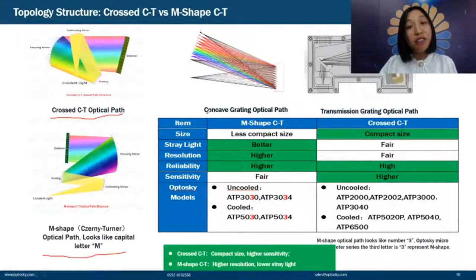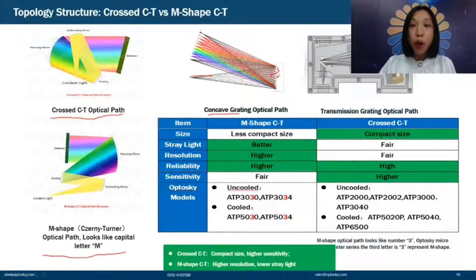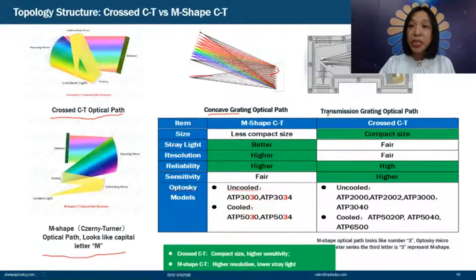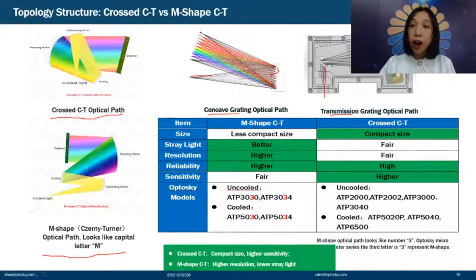We also have the concave grating optical path — a very simple design where the grating both disperses and focuses the light. The transmission grating optical path has light passing through the grating, which disperses the parallel beams. These then turn to hit the focusing mirror, which directs the dispersed light to the detector to transform optical signals into electrical signals.